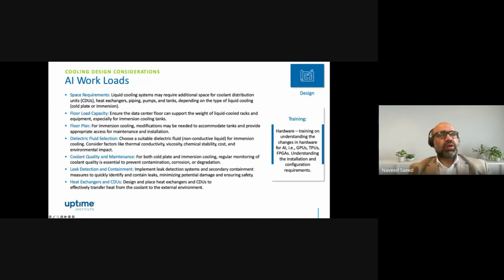So you need to be looking into deeper racks, maybe 1,200 millimeter or 1,300 millimeter racks. Again, it depends what equipment you are choosing. So there are more details that need to be ironed out while making these decisions. Floor loading capacity is going to increase as the densities are increasing, so your floor and structural capacity and your raised floor loading capacity need to be verified before putting these kinds of loads. Floor plan is definitely going to change.